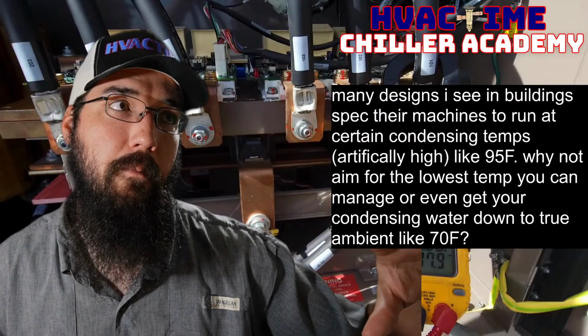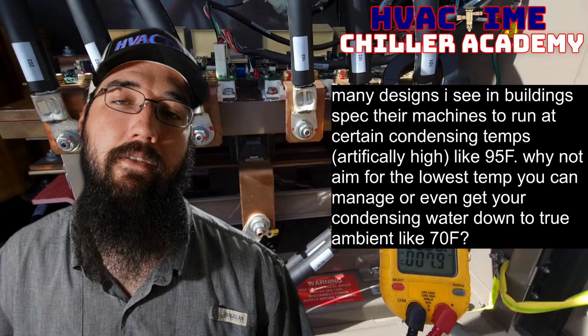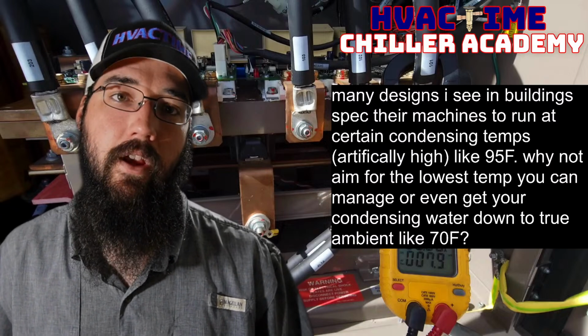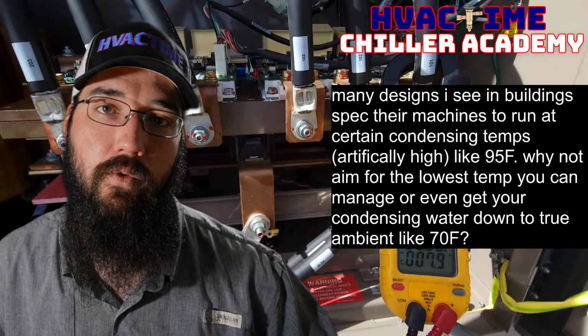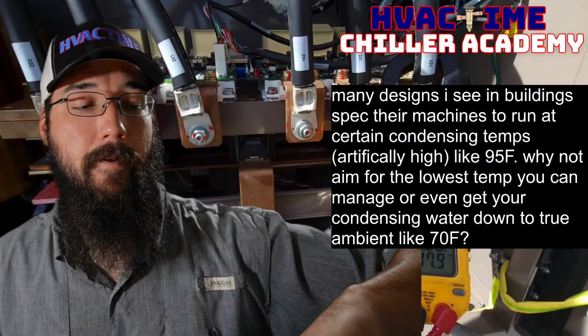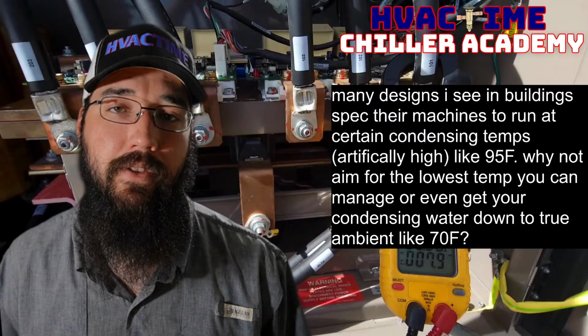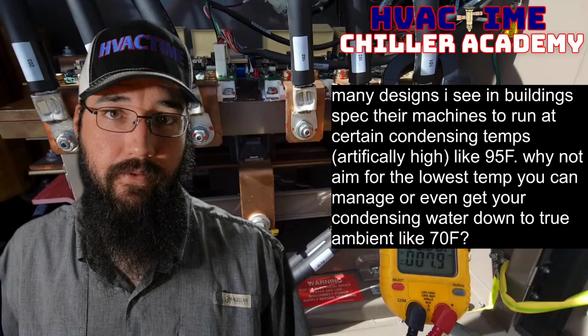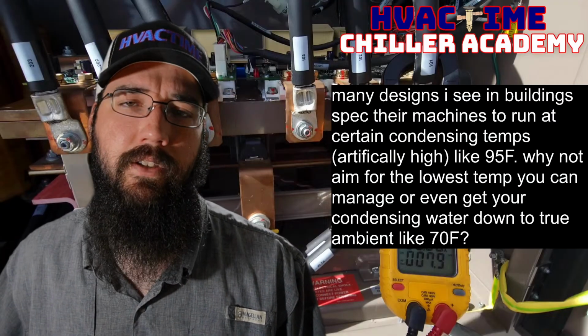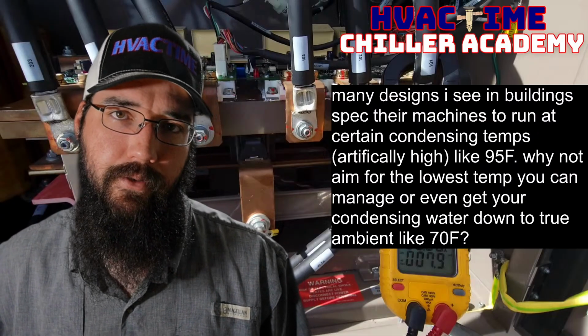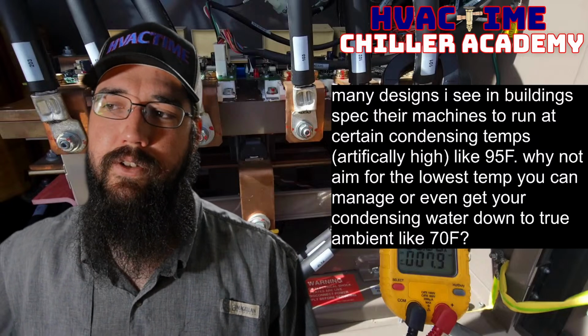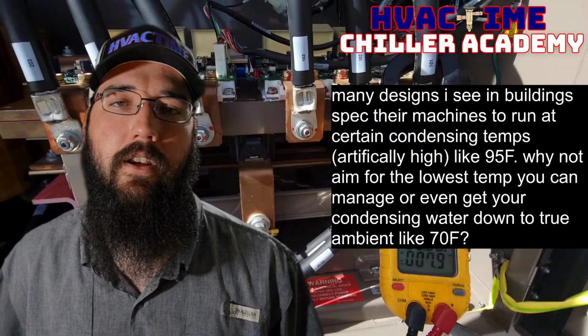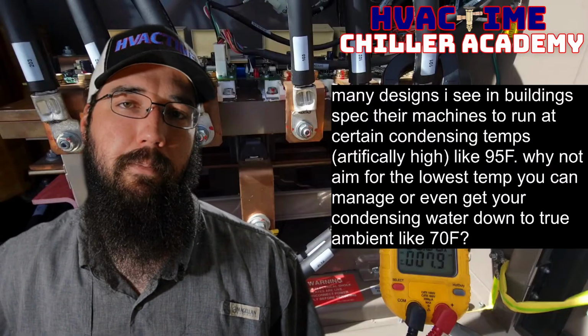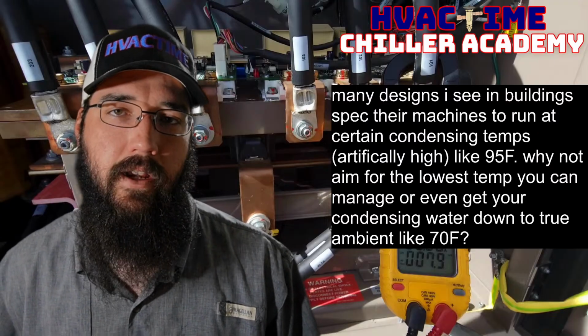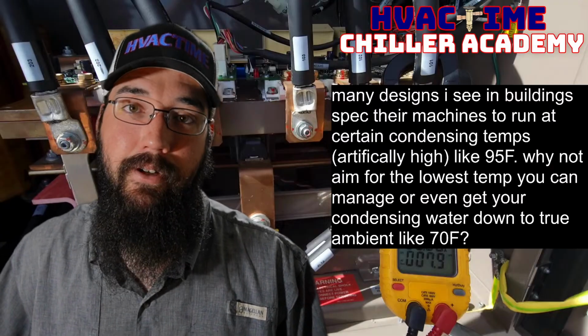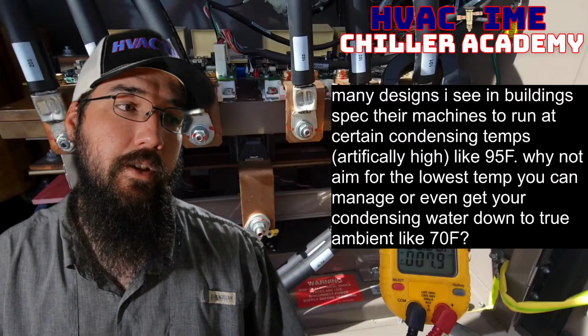Well, now you've substantially increased the likelihood that you're going to end up having a catastrophic failure due to the surging conditions, which is then going to turn into a $100,000+ overhaul, just depending on circumstances, just to get the chiller back online, not to mention the downtime and everything else involved. That's what we're discussing here. That's the difference. So to me, it makes absolutely no sense to artificially run really high condenser water temperatures just to save on the tower fan, where the worst case scenario I've seen is you have to use a helicopter or a big crane to pluck the tower fan motor because of its size and location, right? That still ends up being a lot cheaper than trying to overhaul the compressor. Not to mention all the extra energy you end up using.